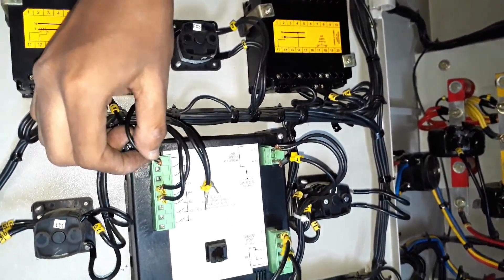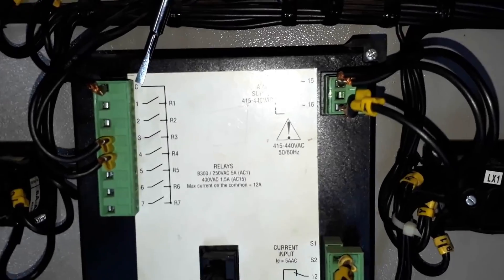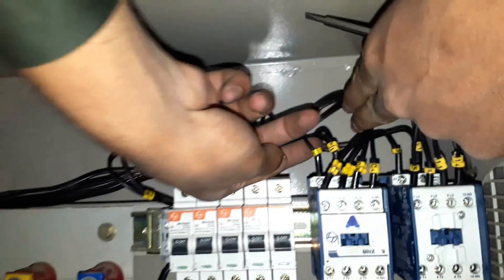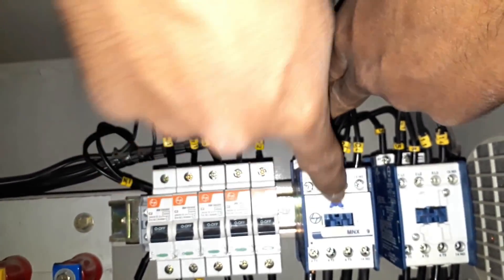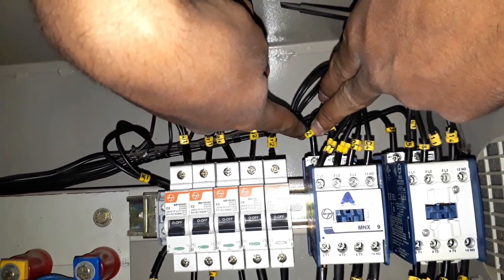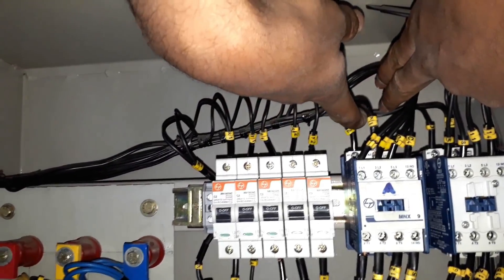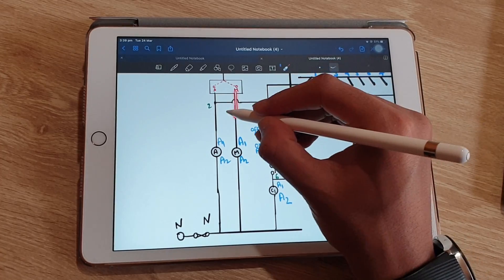As you can see from this panel, from terminal number two it is connected to the common terminal of the APFC relay — as I zoom the camera you can see it is connected to the C terminal of the APFC relay. Two wires are taken out: one is connected to the common terminal and the other wire is connected to A1 of the auto contactor. The A2 terminal is connected to neutral.